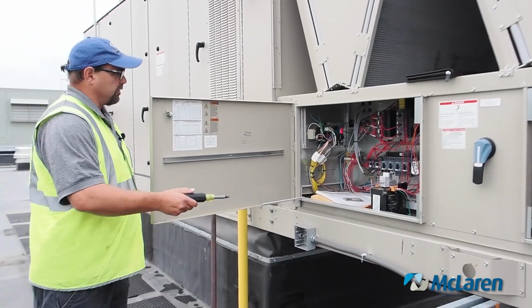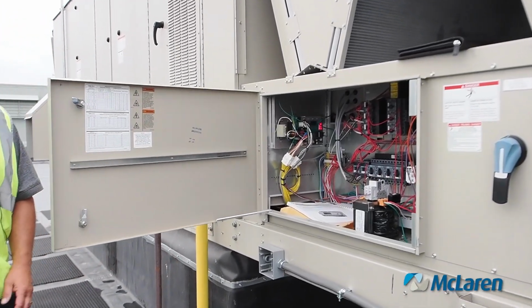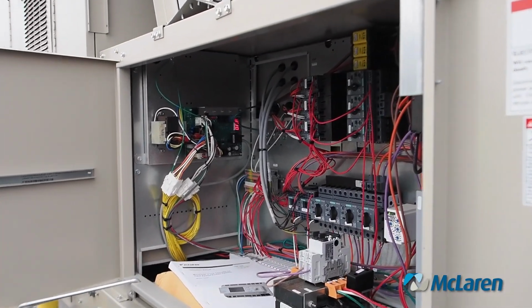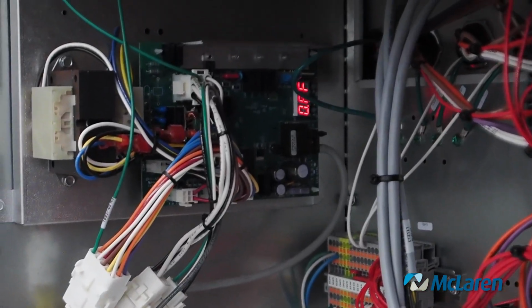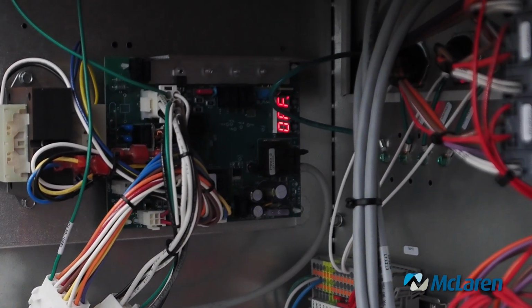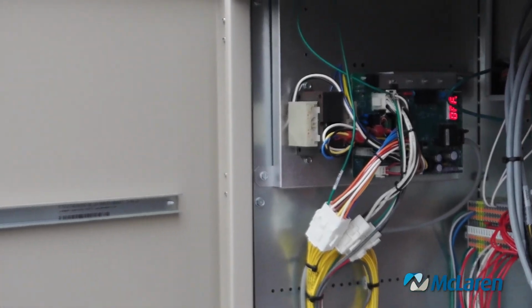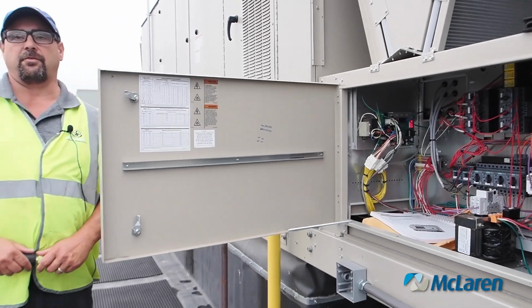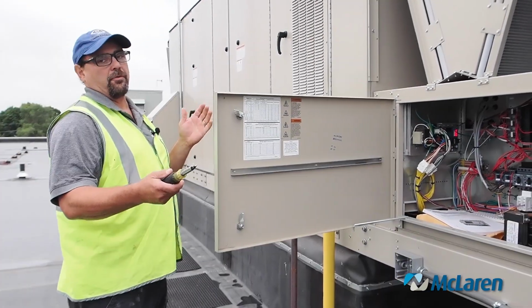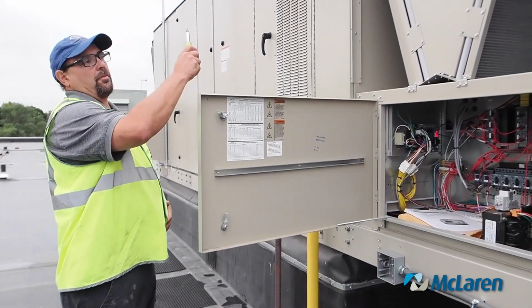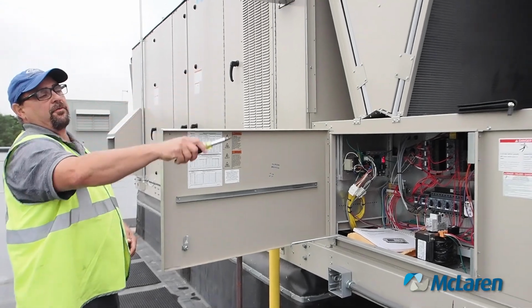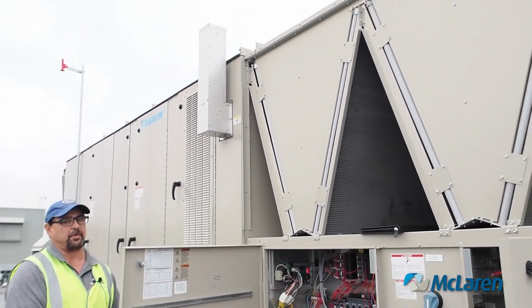Also, I'd like to point out there is a display for the burner section on the left side of the cabinet there. Currently it probably says the word off, I imagine. Yes, we're not calling for anything right now, but that gives you the display on the modulation of the gas-fired furnace. While we're over in this section, I also like to talk about the microchannel condenser that sits above the control panel or high voltage panel here.